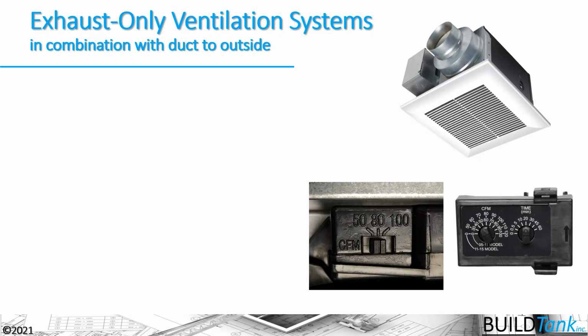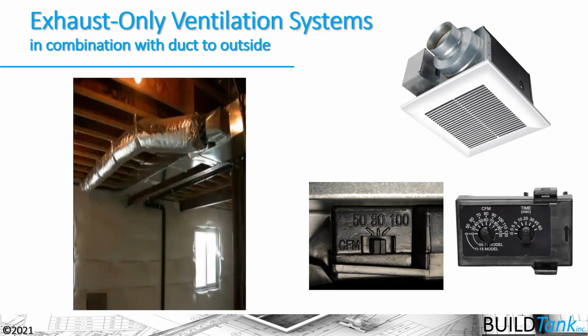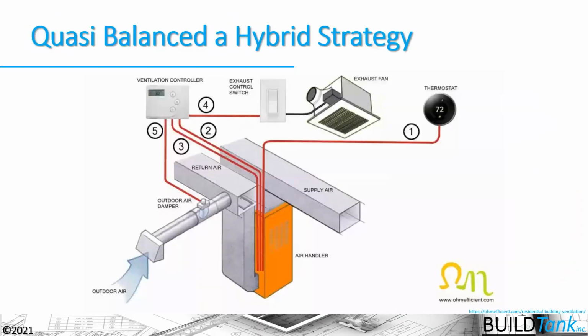Now you can also pair this with a duct running from the outside to the return side of the furnace, so you can have what we call a quasi-balanced ventilation system. If you do this, you want to put that iris damper in so you can match the incoming air to the outgoing air to get that quasi-balanced ventilation strategy. So you can see in this example, there's a damper on the system, so they'll run it intermittently, but ideally on that damper, you can also close it off when you're not running it, or close it off potentially when the furnace fan is running, and you might be bringing in more air, or have the ability to measure the flow across that damper and be able to set the flow rate there.